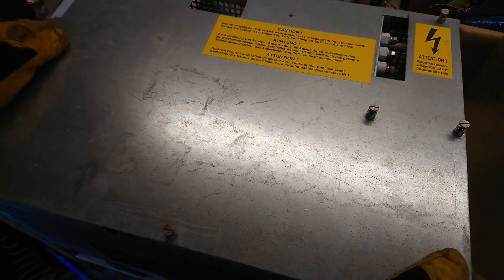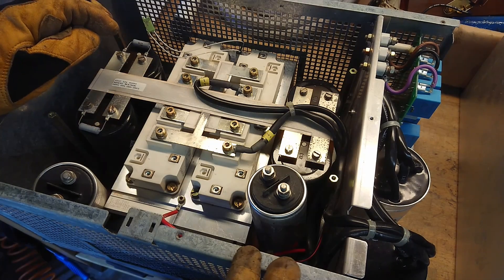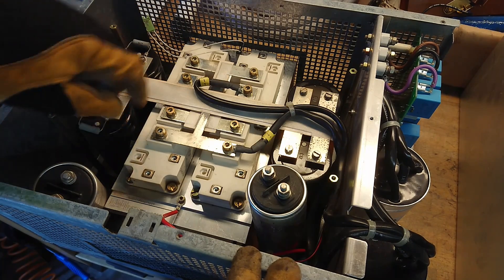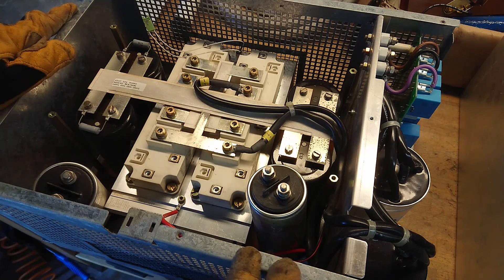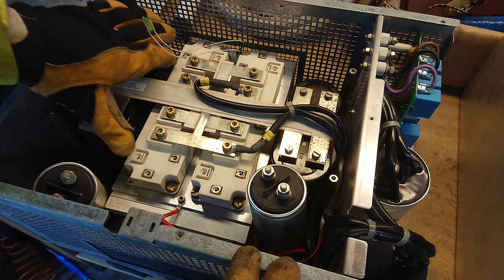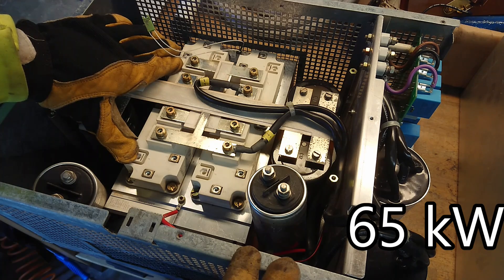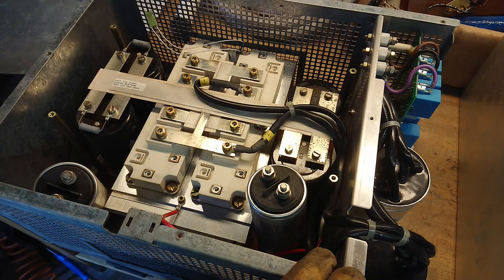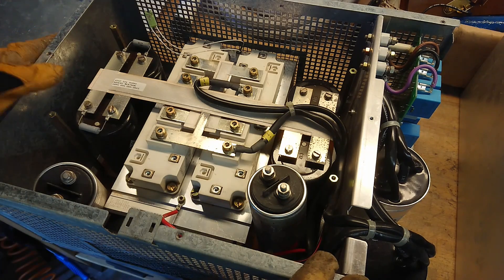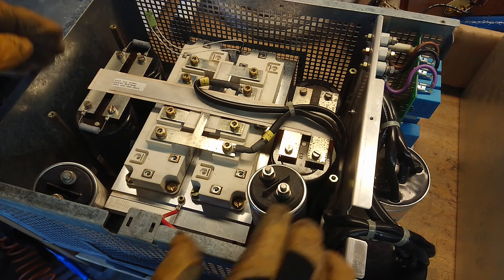Starting with the inverter, we can remove the top lid here. At first we see a full bridge of BSM 400 bricks from Eupec, so this is a pretty sturdy machine. I think this was rated at something like 70 kilowatt or 100 kilowatt. It actually had two of these inverters that would either run one on, one off and switch around if it heated up, or run alternating or in parallel — I actually do not know how that was configured.